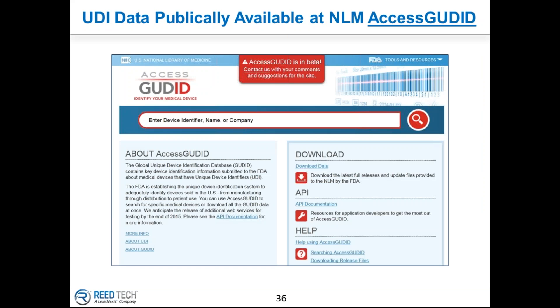After the grace period has been completed, those records you submitted to the FDA are available on AccessGUDID, a public website. There are four or five fields that are redacted, but otherwise it's the data you submitted, made available publicly. You can do searches, find the data, confirm it, and actually poke around to see what other companies in your sector have submitted. That is one of the final confirmations that your data has been actually published.